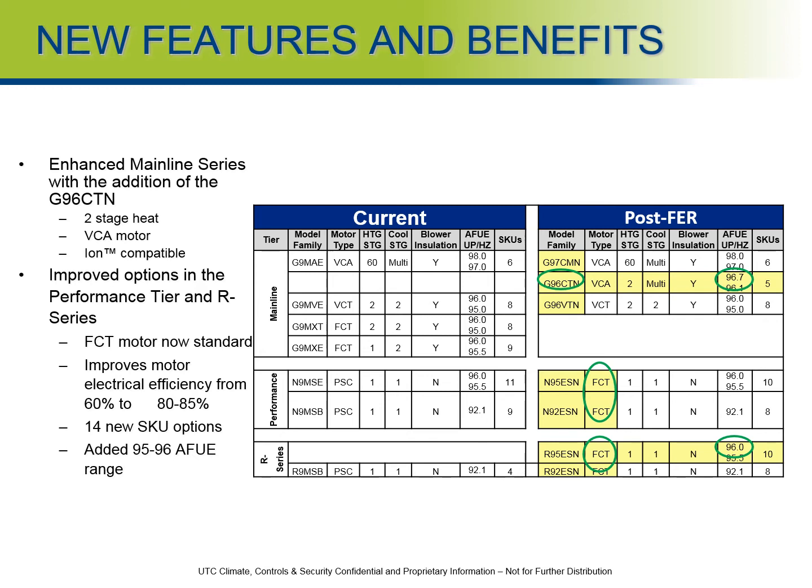Some of the other things that we've seen going to the different model lines in the blowers is the type of signal that the motors receive. We're going to break down into three different types. Initially, there were four different types before the FER rule came into play. As we all know, at this point, PSC motors have been phased out. They were phased completely out of manufacturing as of July 2019.